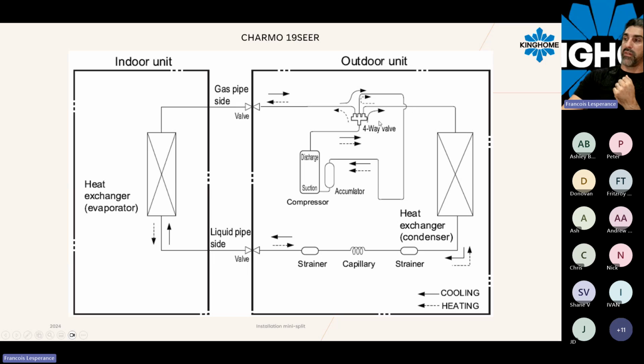So this four-way valve will be de-energized in cooling mode, and the U-bend heater portion will stay on this side of the four-way valve. Our discharge line will go through that four-way valve, going out here on the third pipe and directly to the condensing unit, so on the condenser. The condenser will do its job and push out the heat of the refrigerant, changing its state from vapor to liquid. On the other side here, we have high pressure liquid refrigerant.